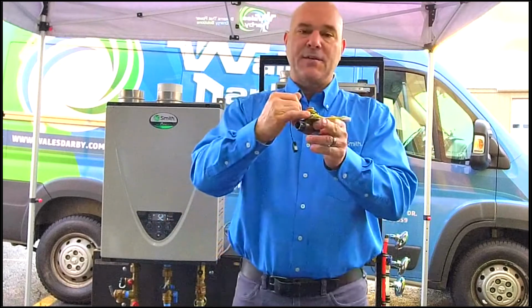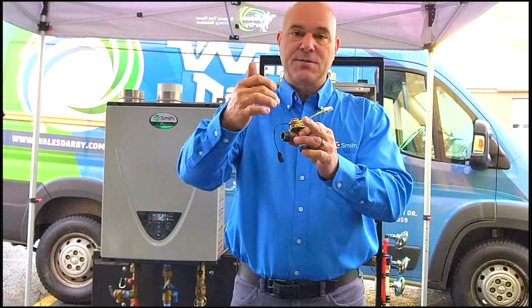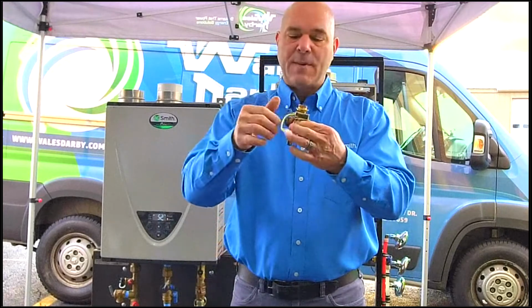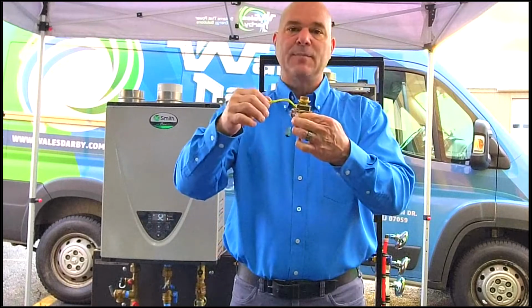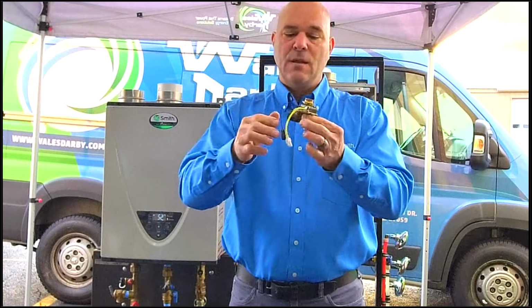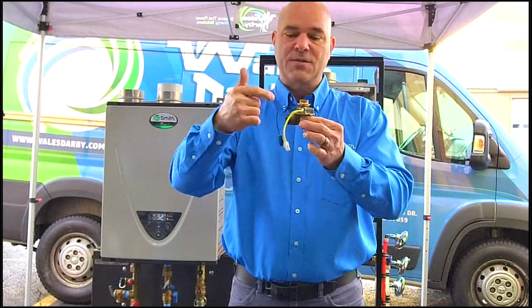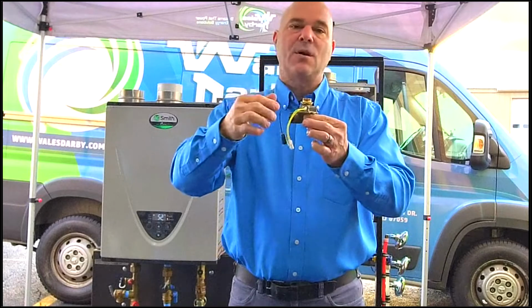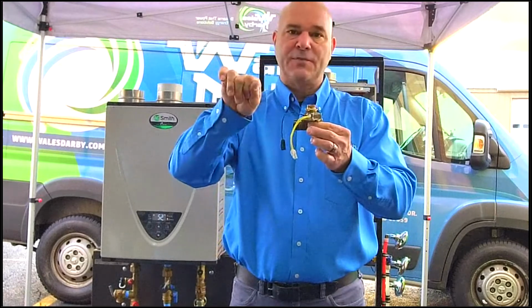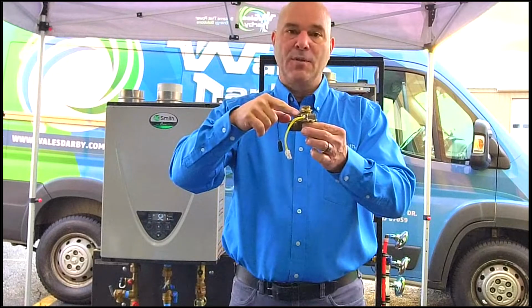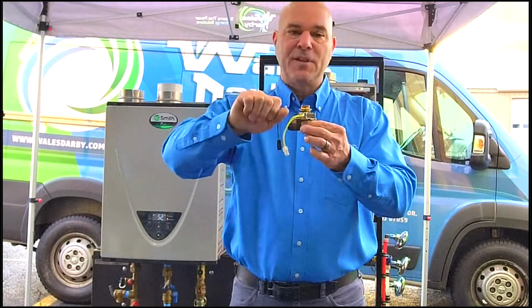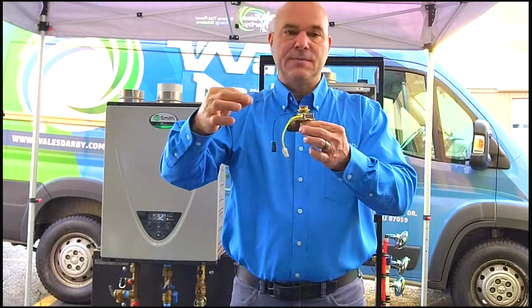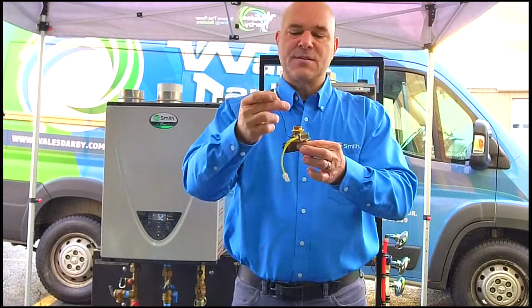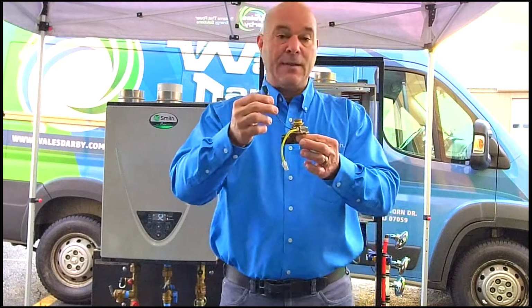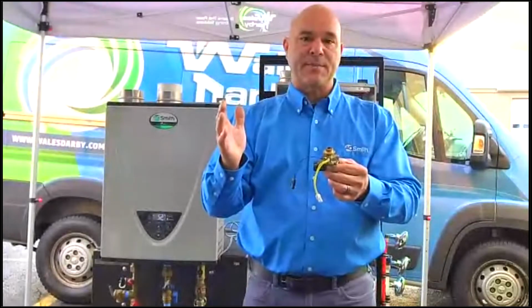In the center, there's a Phillips head screw. That Phillips head screw is removed. The thermistor will come out and the heater block will come out. The heater block is in a dry port. The thermistor is in a wet port. There's an O-ring on the inside of the thermistor. So if you have to change out this thermistor, you have to shut off your mains and drain it in order to pull the thermistor out. So back out the Phillips head screw. This will come out and it can be replaced. This is nothing more than an ohm value, and I can't give you the ohm value because it'll be based on temperature. Okay, so that's the cold water inlet.